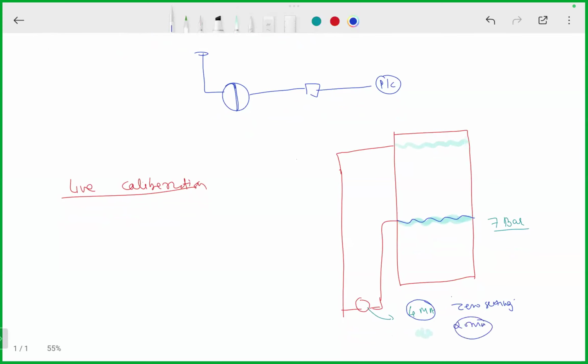If it is not produced, adjust by span setting. Sir, just one question. When we are at the low level alarm, it means the pressure is also getting low, right? Then how will it maintain 7 bar? For auxiliary boilers, the pressure we maintain is 5 to 6 bar. When the low level alarm comes, the pressure falls.